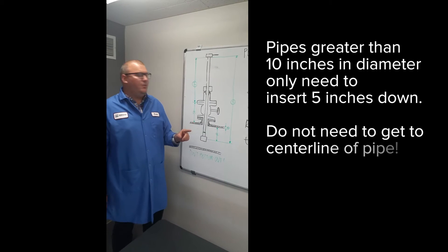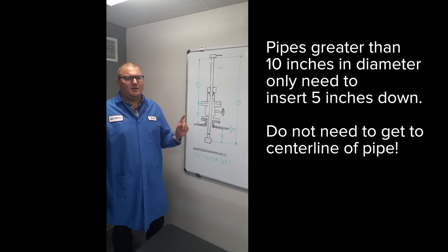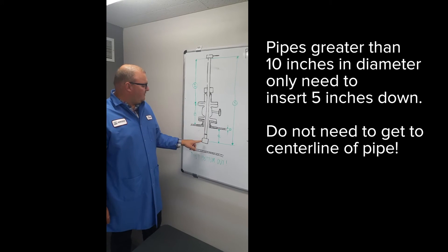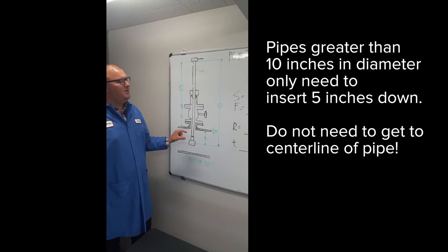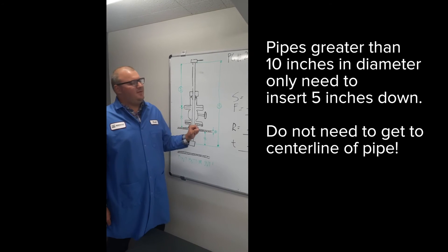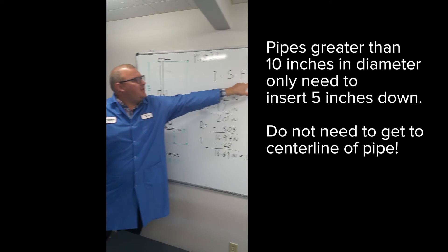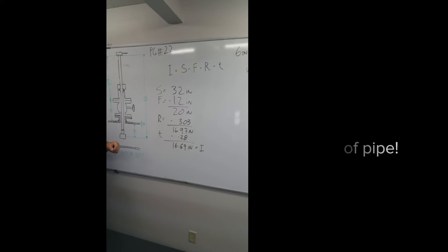It's important to note when inserting into pipes greater than 10 inches that instead of trying to get to the center line of the pipe, we just want to insert 5 inches down. In those cases, you replace your R value with 5 inches and that's clearly stated in the manual.